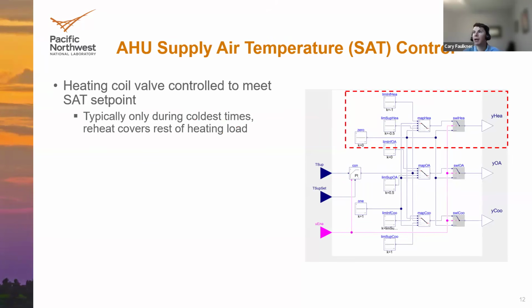Now, typically, I mentioned, these VAV systems have reheat downstream, and the supply temperature might be something just constant like 55 Fahrenheit. And so because of that, you're typically only going to need heating at the air handling unit during the coldest times, because the reheat can cover the rest of the load. So it's really when you're bringing in enough cold outdoor air that when it mixes with the return air, it's going to drop the temperature low enough that you might need a little bit of heating to meet that supply air temperature set point.